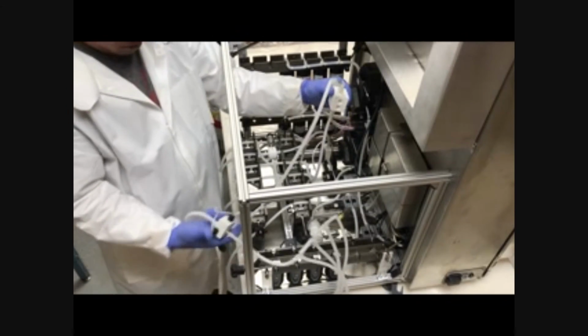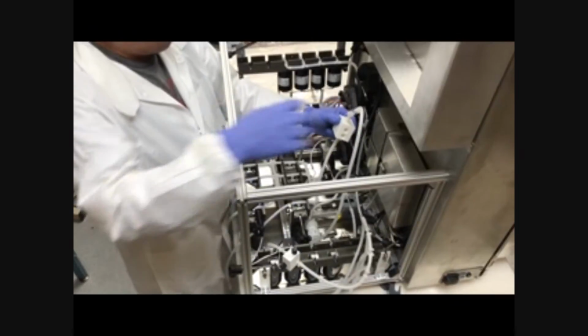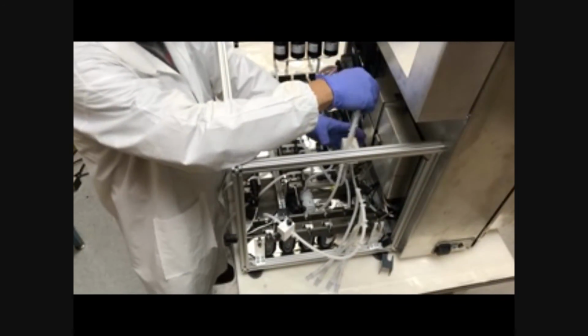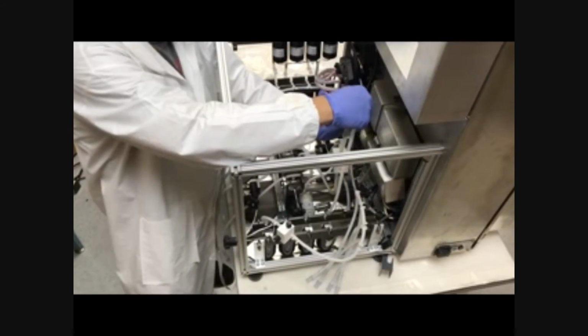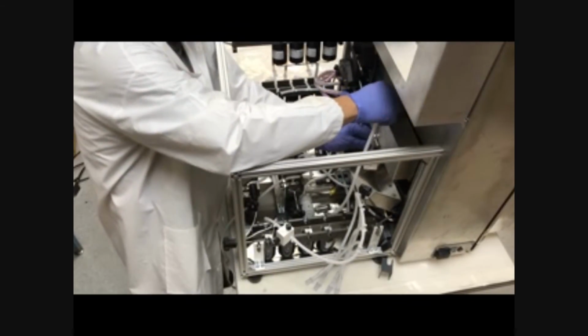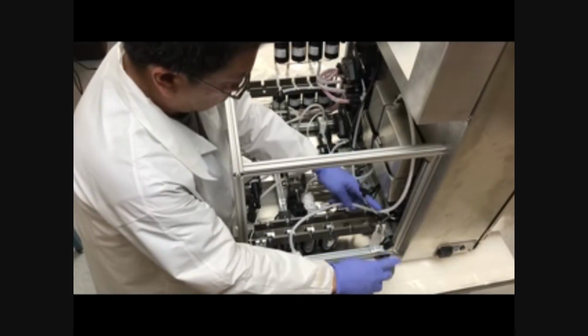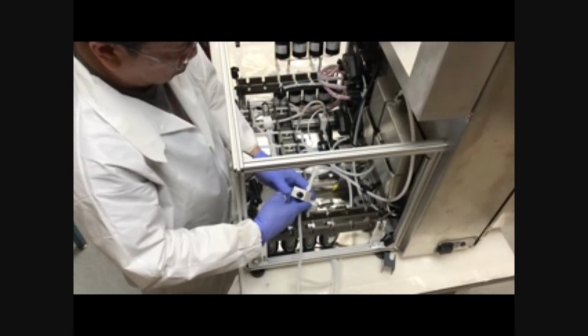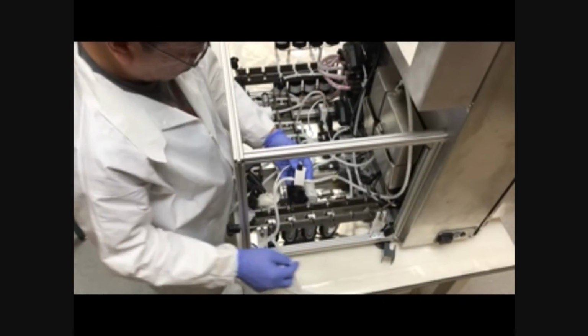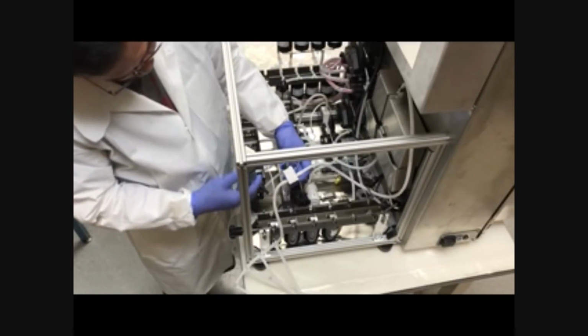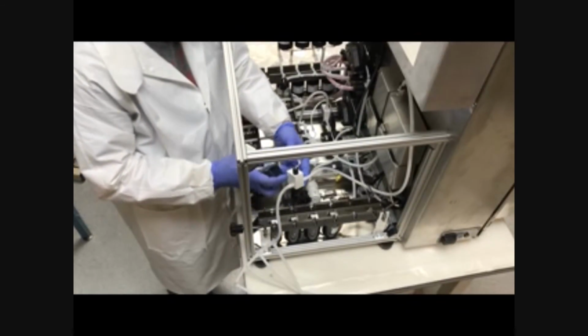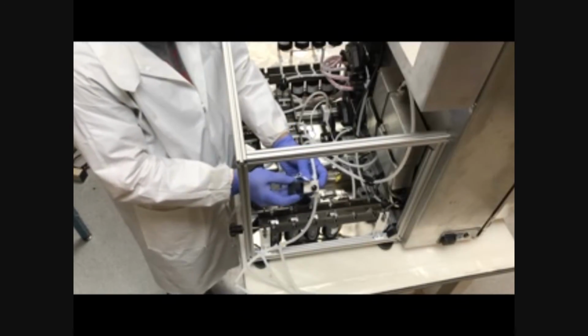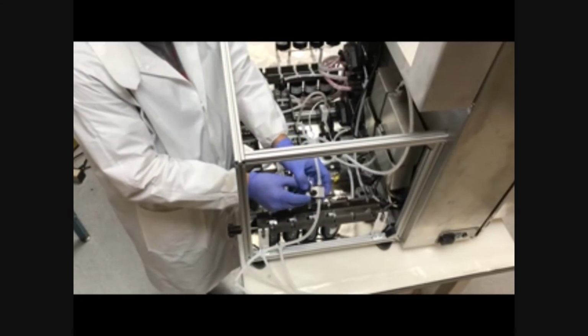So now what's left is post column. We are going to install the UV flow cell and the pH flow cell. So the UV flow cell just slides into the slot in the UV detector, and the pH flow cell is right below that. And the tubing, so the flow goes down from the pH flow cell, comes up through the UV sensor and into the conductivity sensor, which he's putting a clip on now. So there he installs the clip.